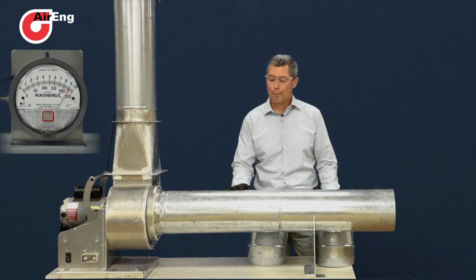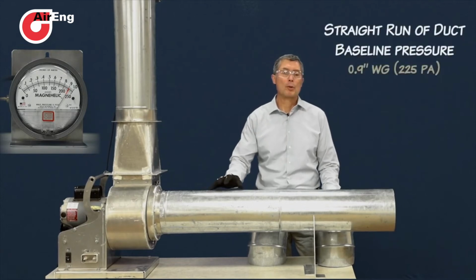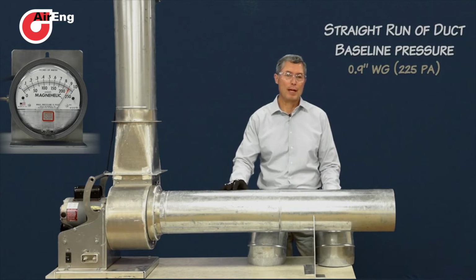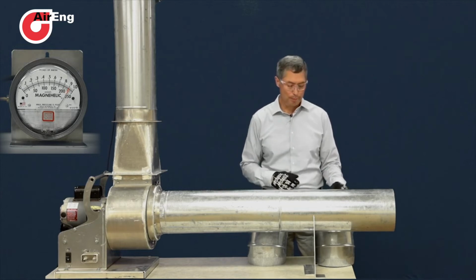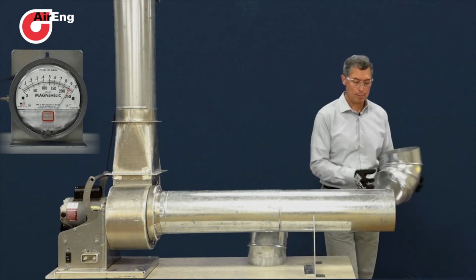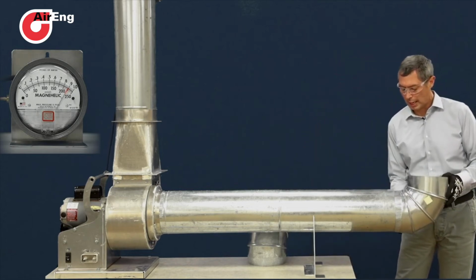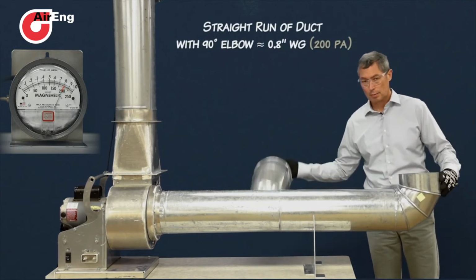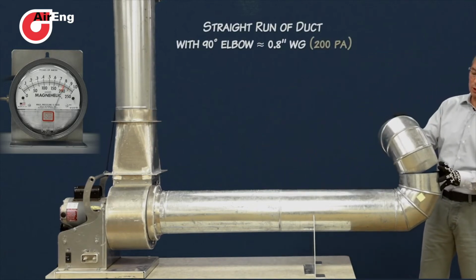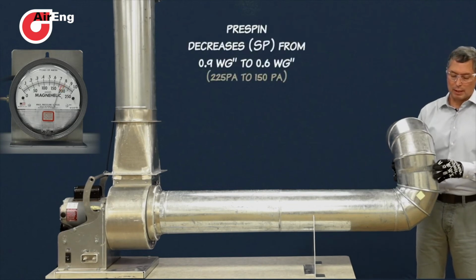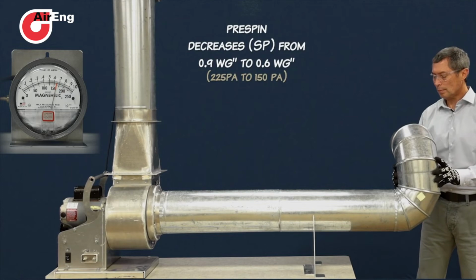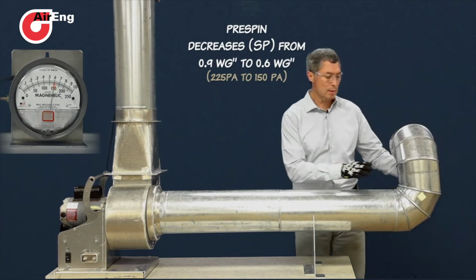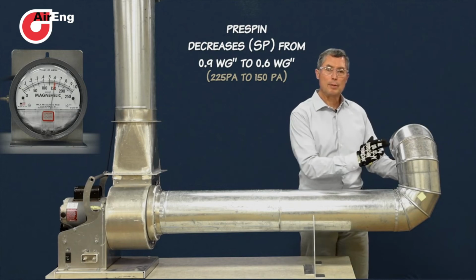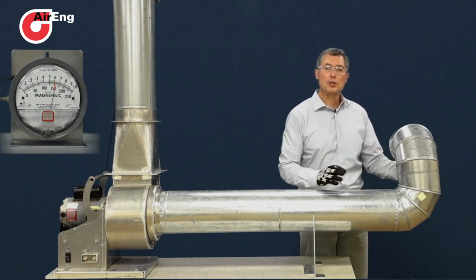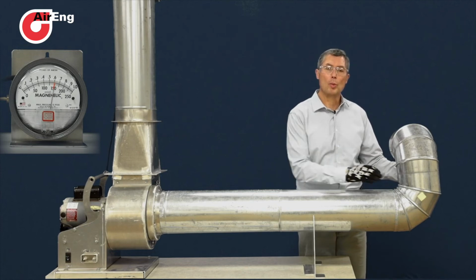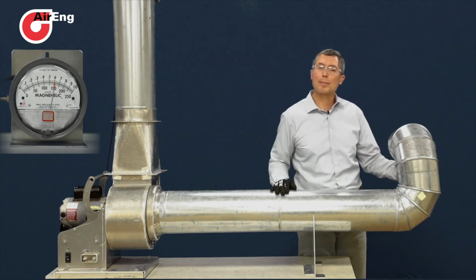On to the second part of our demo. What we've introduced is a straight run of ductwork, and we're going to see if that affects or changes the way the fan performs with a pre-spin corkscrew. So put this onto the inlet. Again, this is our 90-degree elbow here. No vanes, just a 90-degree elbow. And we're going to put this second elbow on in the pre-spin configuration. Notice during performance that despite this run of ductwork, the pre-spin elbow configuration is almost the same exact performance as what it was when we had this at the fan inlet. And we'll talk about that in our final thoughts.